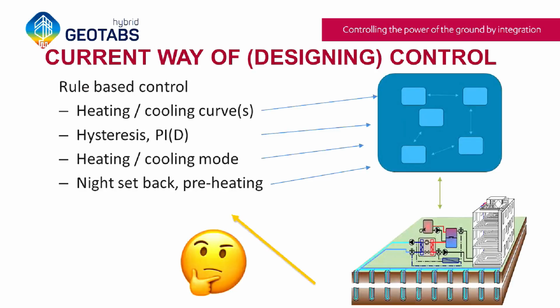So this is so far for the introduction. Now let's go really into control of buildings. The general way of controlling a building is we have an HVAC system, and then we control it with what's called a rule-based controller. The rule-based controller is a set of typical blocks, such as heating and cooling curves, some hysteresis, PI controllers. Often, if we have a slow system like TABS, you also need to define the mode of the building, whether it's in heating mode or cooling mode, and make sure you don't switch too fast from one to the other. You may also have night setback and preheating.